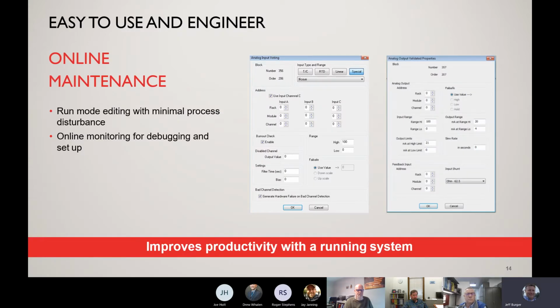We were talking a little bit about the online maintenance. So obviously you can edit in runtime mode. That's another big thing. If you wanted to add, for example, this block over here on the right-hand side is an analog input block. And let's say, for example, you're doing an application, you want to add another thermocouple to the appliance that you're controlling.